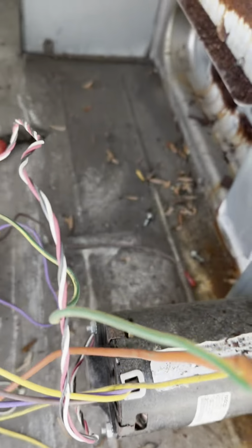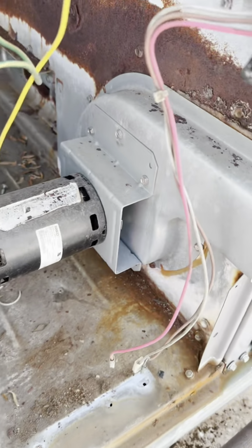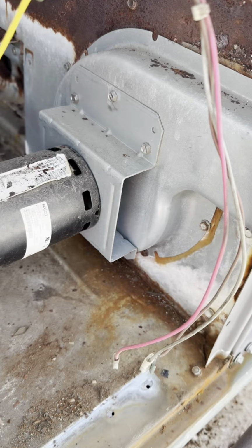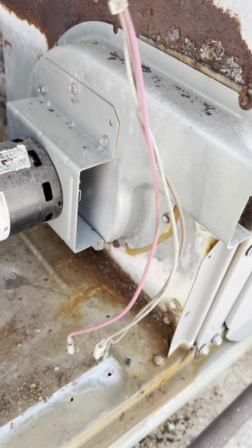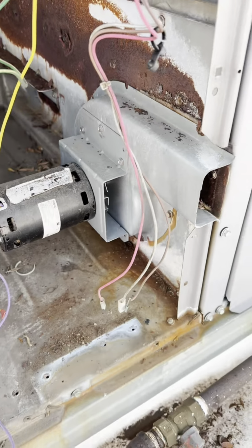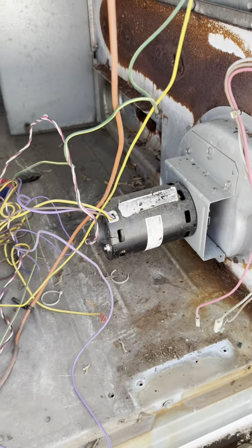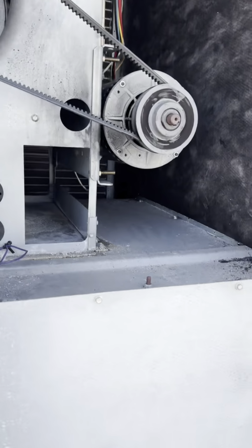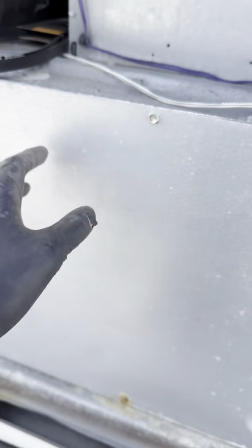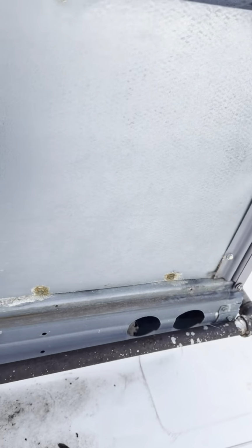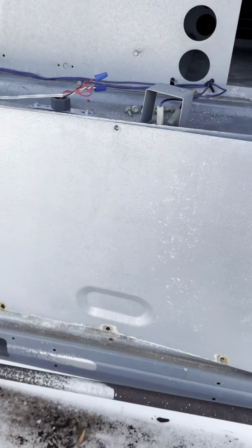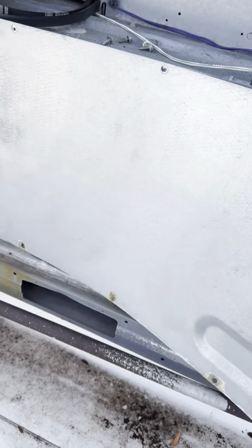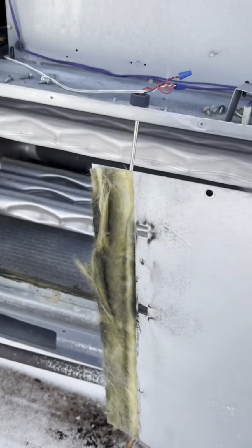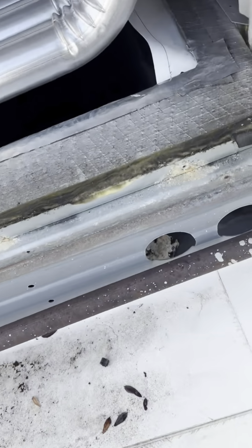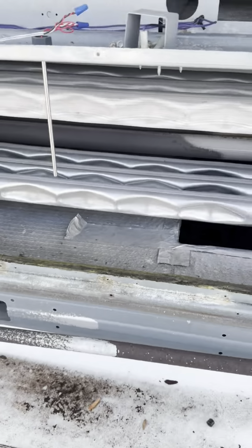With the burner out of the way, we're going to go ahead and remove the inducer motor by taking out some screws to get it off the plate. Remove the blower door and take off the supply side panel to get into the heat exchanger. Once you remove the screw, pull off the side panel. There's the heat exchanger.